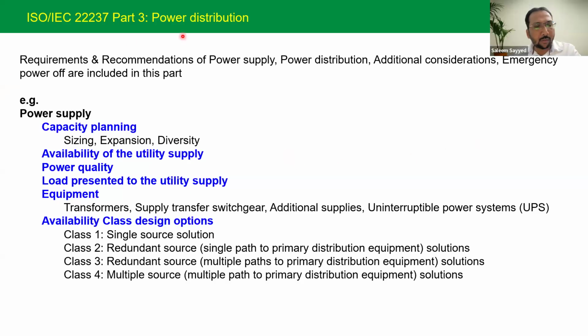I think you picked a very right question on this slide, the challenges in the power supply. Before I go into answering your question, I would like to highlight a few points. The standard gives you the classification of class 1, 2, 3, 4, and the high-level single line diagram of each class, but it never tells you which class to use where. Point number two, there are three standards globally available: IEC, Uptime tier, and TIA 942. TIA 942 talks about rated 1, 2, 3, 4, Uptime tier 1, 2, 3, 4, and IEC class 1, 2, 3, 4.